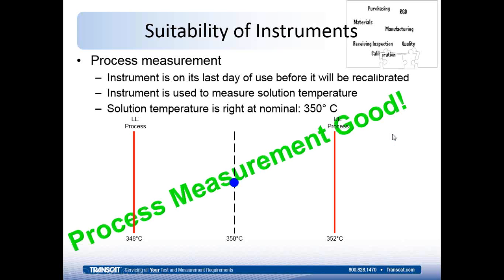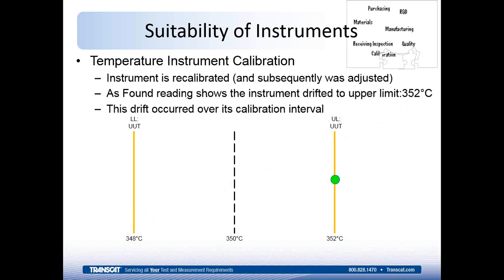And I call that measurement good. Then I send it in for calibration, and it's found that it's at its upper limit, and then it's adjusted back to nominal. So it's found at 352 degrees, and it's brought back down to 350. Now, that may not be a realistic example of an instrument over its cal interval to drift to its full tolerance, but let's just say in this example that it does, for sake of discussing what happens to the process measurements where the instrument had been used over its last cal interval.